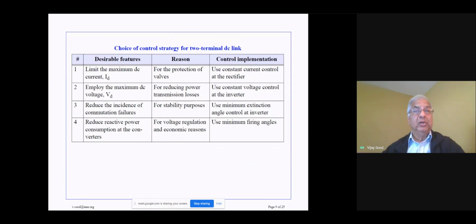The valves have a very low thermal inertia, so we do not want to have too much extra current flowing in the valves. So in order to protect the valves, the maximum DC current must be limited. This suggests a control implementation that, in order to have a constant current controller at the rectifier, would be the best control mode.